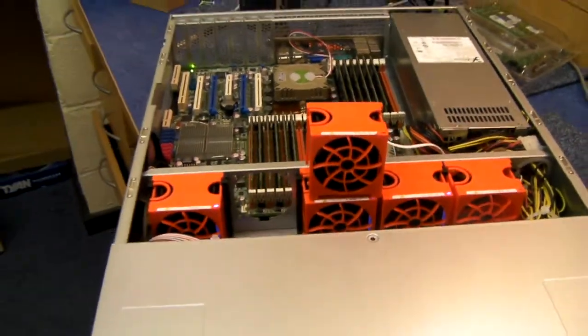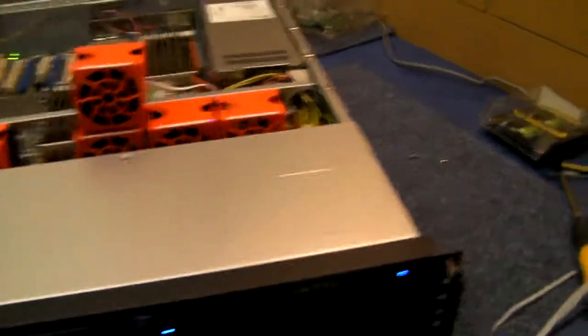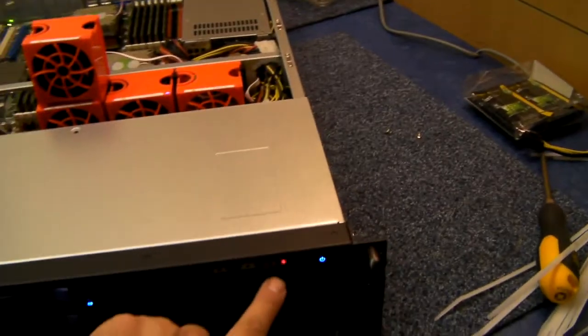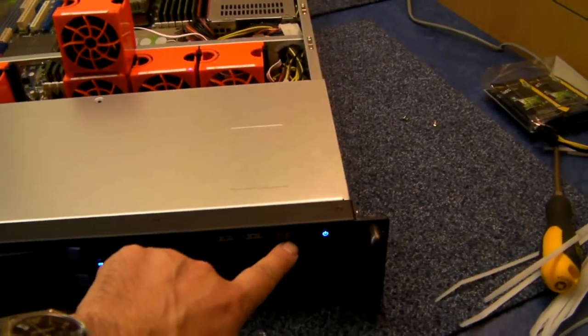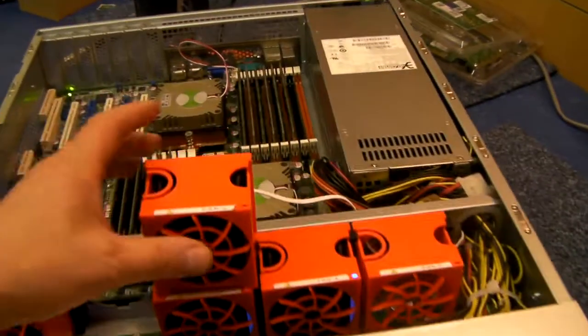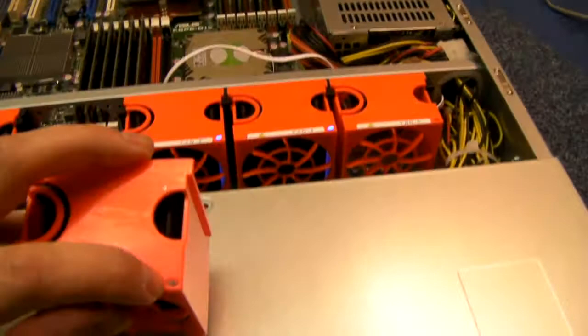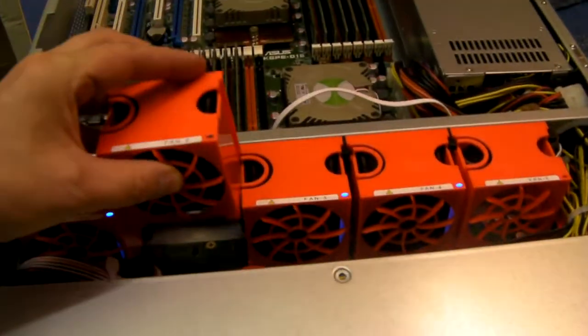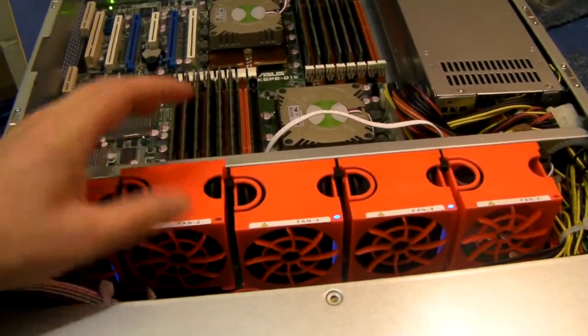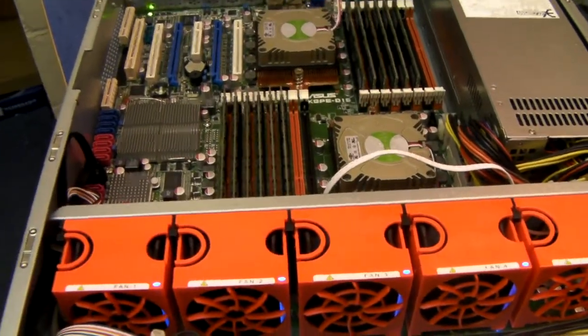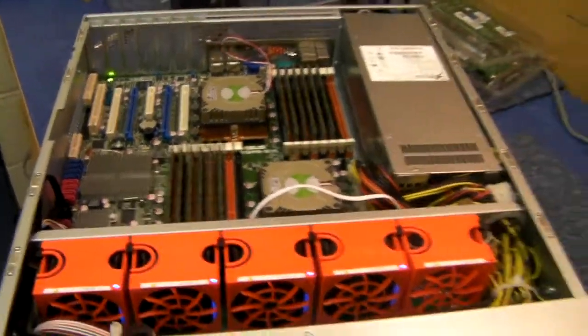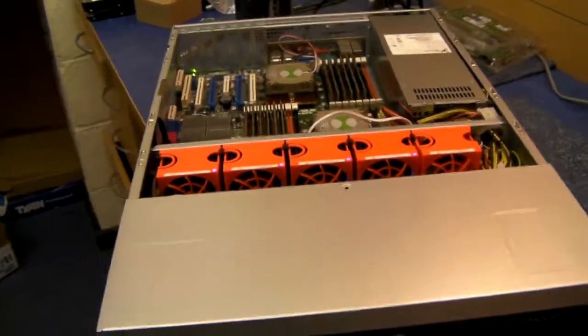So if that fan had just failed you'd get an LED at the front, and there's also an LED on top of the fan which would flicker red. Put it back in and everything's happy.